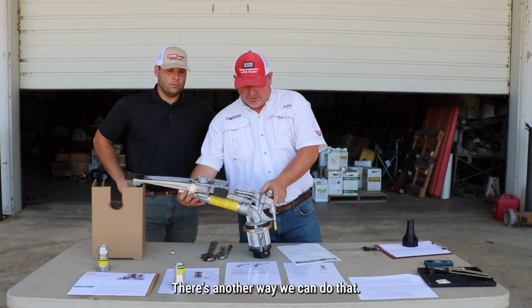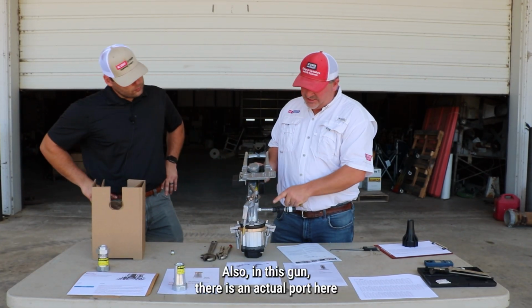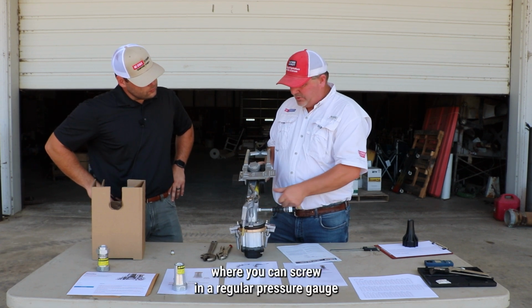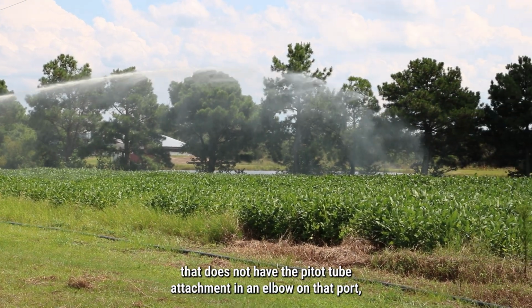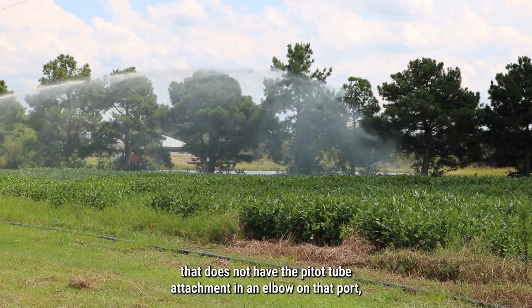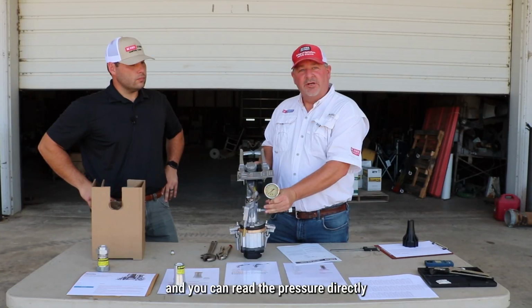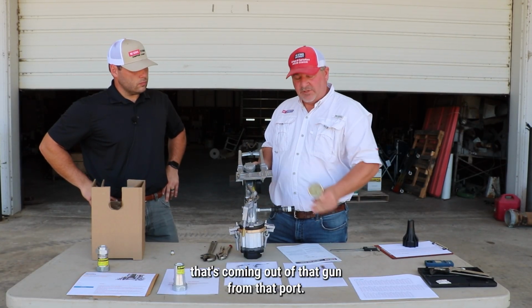So he was able to show how we check pressure during operation with a pitot tube. There's another way we can do that also on this gun. There's an actual port here where you can screw in a regular pressure gauge, without the pitot tube attachment, into an elbow on that port, and read the pressure directly as it comes out of the gun.